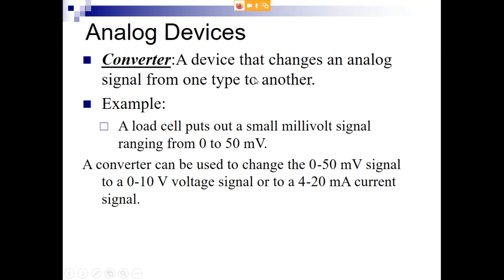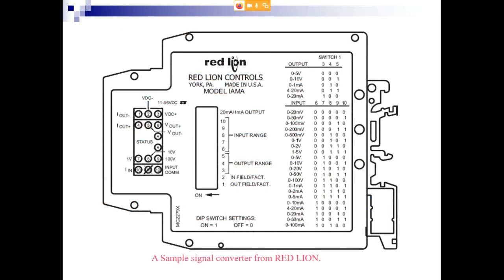When you buy a sensor, you need to know what signal it outputs. Many transducers only put out a millivolt signal, which attenuates very quickly because it's so small. You need to convert it to a higher voltage — say zero to ten volts — or ideally a 4 to 20 milliamp signal. The way to do that is with a converter. A converter is a device that changes the analog signal from one type to another — note that's bold text, so expect a test question on it.